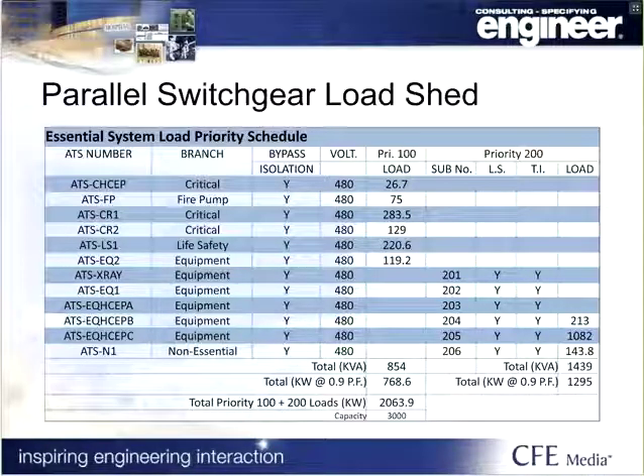And as you can see, we're looking at it in 2 different ways in this scenario. We're looking at the priority 100 load, which is the load that has to be on in 10 seconds. And that load needs to be less than however many engines you can get on in 10 seconds. Most manufacturers would say they can get 1 engine on in 10 seconds. Some manufacturers will say something else. But it would have to be tied to the quantity of engines you can get on in 10 seconds. And then priority 200 would be anything I can get on after that 10 seconds.